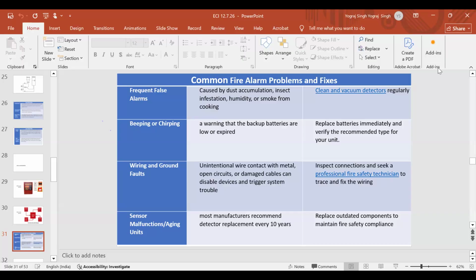Now, every building will have a different architecture. But here, suppose I have provided 20 detectors at some location. My control panel will only know that out of 20, number 16 has activated. But where this number 16 is will be known through these panels. There is something called a mimic panel, and there is something called a repeater panel. The mimic panel is inside the building, where it shows different wings and floors where these things are marked. So you will come to know that there is fire in the east wing, third floor.